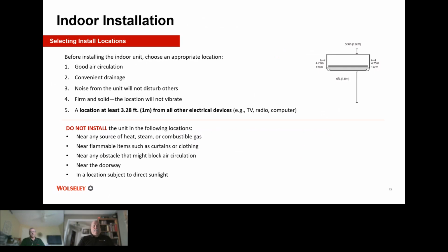So do not install in the following locations: near any source of heat, steam, or combustible gas, near flammable items such as curtains or clothing, any obstacles that'll block the air circulation, near the doorway, in a location subject to direct sunlight. The reason for the doorway or even a window sometimes is that a lot of these mini splits have the thermistor that reads the temperature at the head. So if you get a draft on that head, it'll throw the temperature off and it'll think you need a lot more heat than you actually do because of the draft.